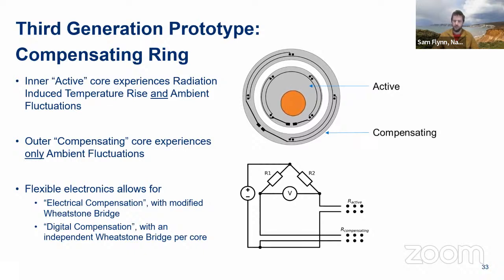We built this with flexible electronics in mind so that you can either do a direct electrical comparison of the two. If you're familiar with electronics, you'll see the circuit below. That's directly comparing the resistance of the inner ring and the outer ring. Alternatively, we can hook the compensating ring up to its own Wheatstone bridge and have a digital compensation. That's an area we're still looking into, which one provides the best certainty and is most robust. I'm going to share some results of this now.